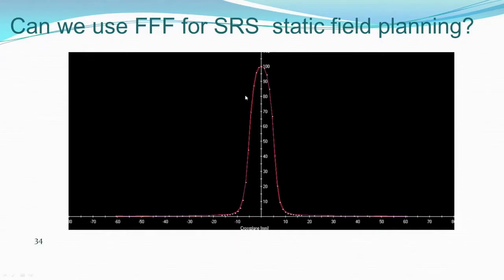So what I did was I compared the profile of double F and triple F and looked at where it actually changes. So this is for a 1 centimeter beam profile and they both overlap. So if I'm treating a 1 centimeter lesion or less than that, I can use the triple F profile. It will be the same as a double F profile, but the advantage I will get is less treatment time, right? I can still do static 3D CRT type of SRS.